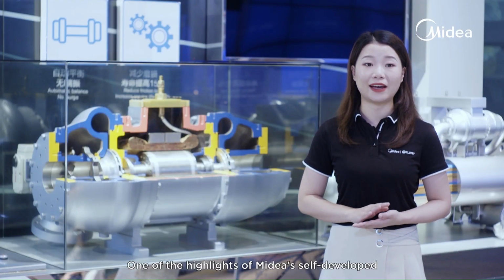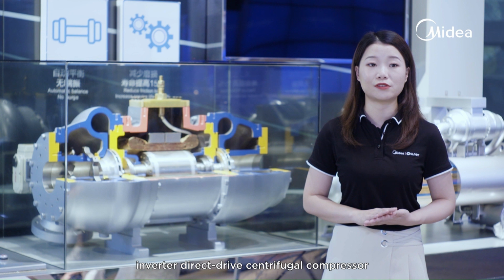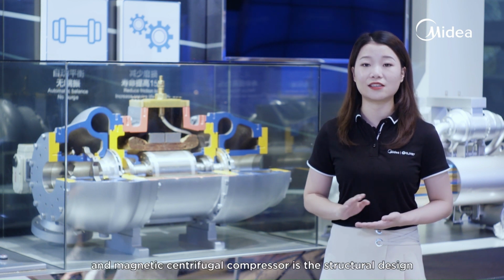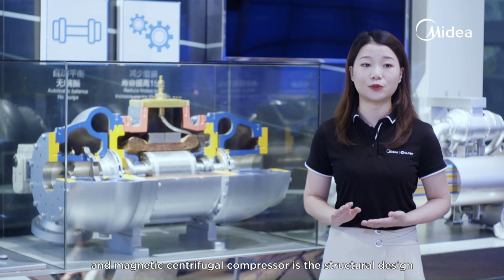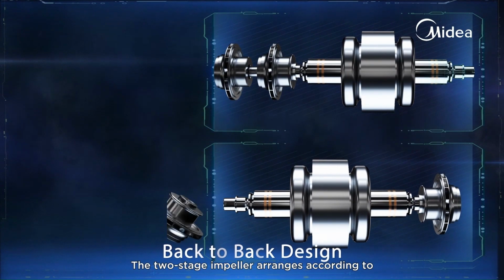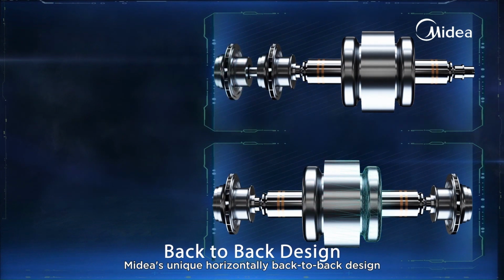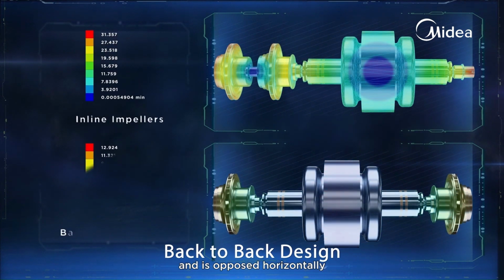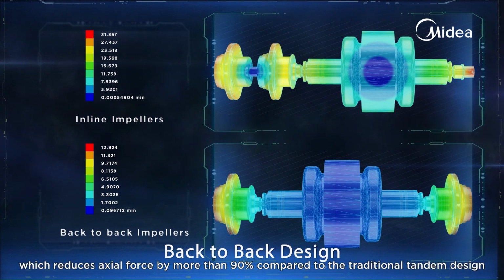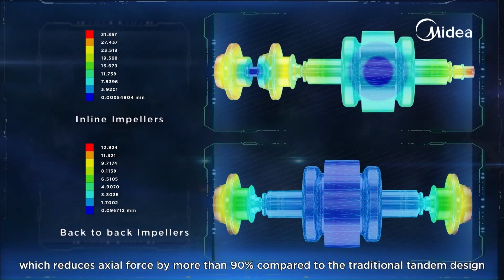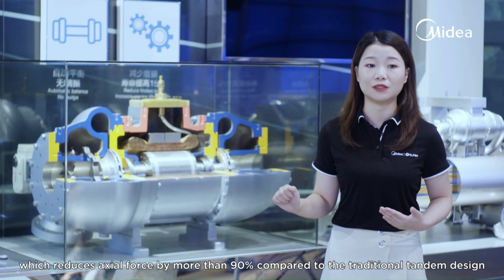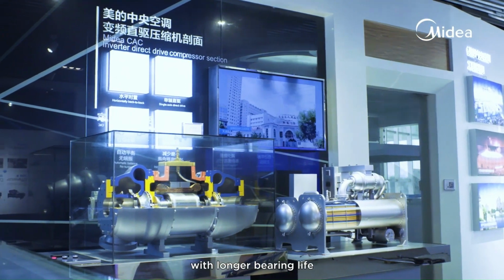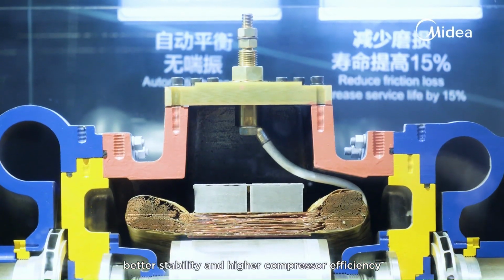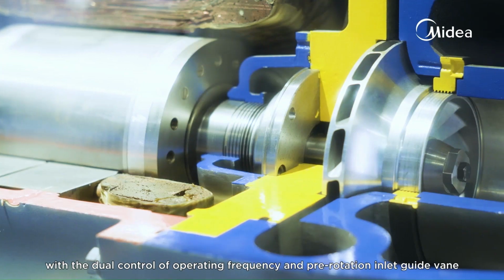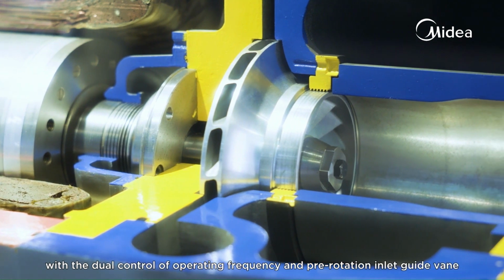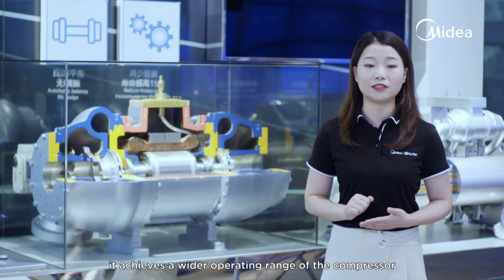One of the highlights of MIDEA's self-developed inverter direct drive centrifugal compressor and the magnetic centrifugal compressor is the structural design. The 2-stage impeller arranges according to the MIDEA's unique horizontally back-to-back design and is opposed horizontally, which reduces axial force by more than 90% compared to the traditional tandem design. With longer bearing life, better stability, and higher compressor efficiency. With the dual control of operating frequency and the pre-rotation inlet guide vane, it achieves a wider operating range of the compressor.